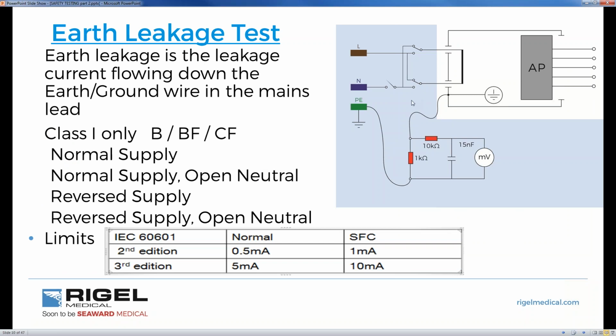I'll go further into detail on how it works with the medical device under test, which is here, and our Rigel device. The Rigel device in this picture is in blue. Everything in this schematic is internal to the Rigel device. And I'll explain this further: when we're looking at earth leakage and the flow of earth leakage within a medical device, we have to measure that, and it's measured via the safety analyzer. So in this presentation I will talk through where the current flows, from A to B, and how things are measured.